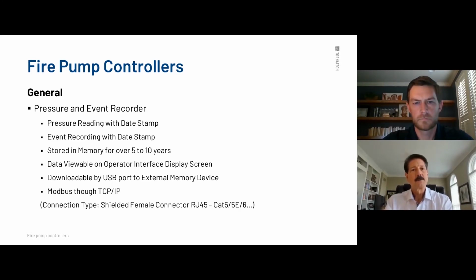We also have a downloadable USB port. And what's nice about that is you don't have to open the door. All you have to do is unscrew a little cap and insert a USB, a couple keystrokes, and you can download all the data that's required to your USB without even opening the door. One minor comment on that is, of course, without opening the door, you don't have to worry about any arc flash potential with live incoming cables.